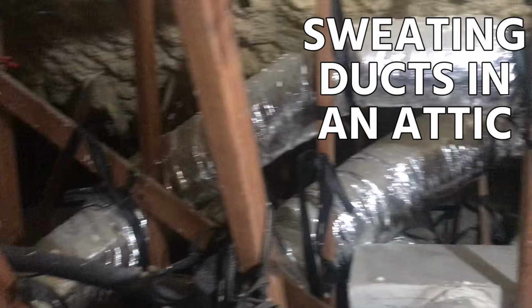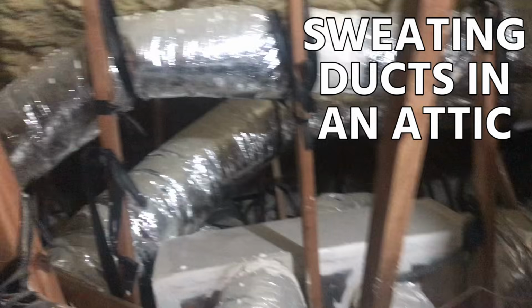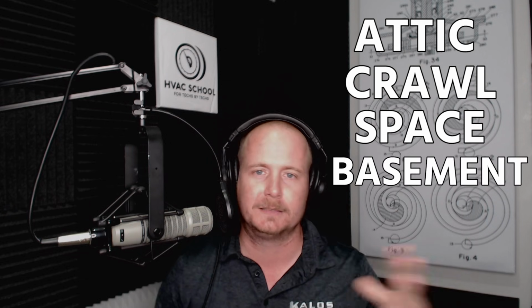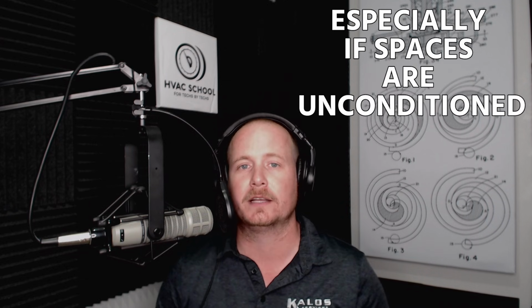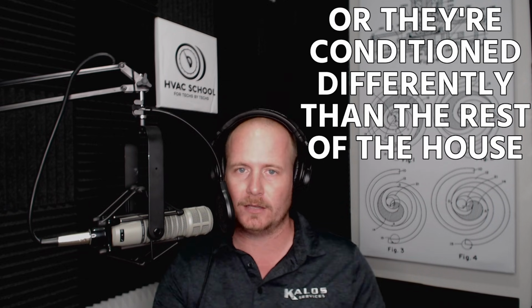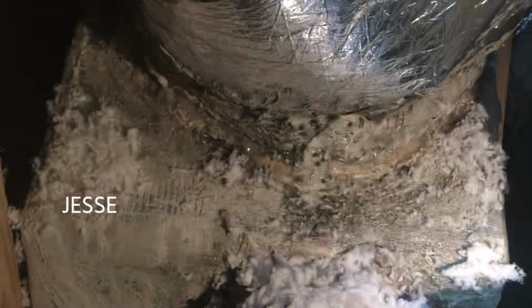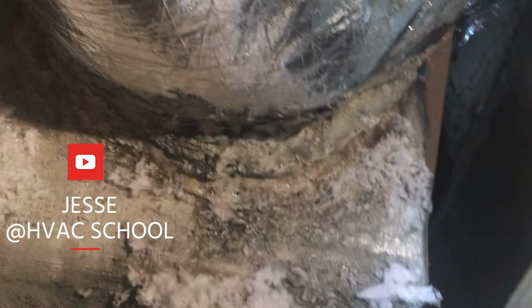Item number 2 is sweating ducts in an attic. And so sweating ducts in an attic is a completely different category of problem. Attic, crawl space, basement, especially if those spaces are unconditioned or they're conditioned differently than the rest of the house. So here is the supply plenum, the original supply plenum for downstairs. This is all original ductwork here. And there's just moisture that's building up.